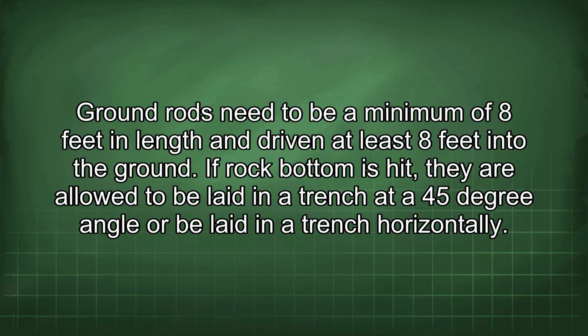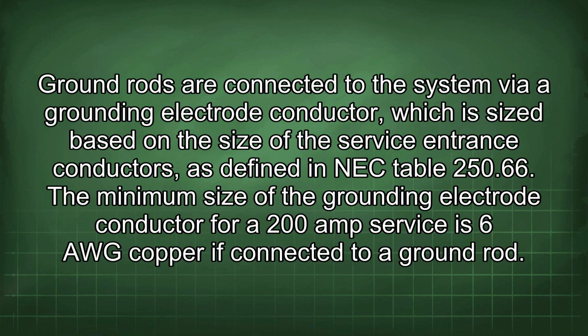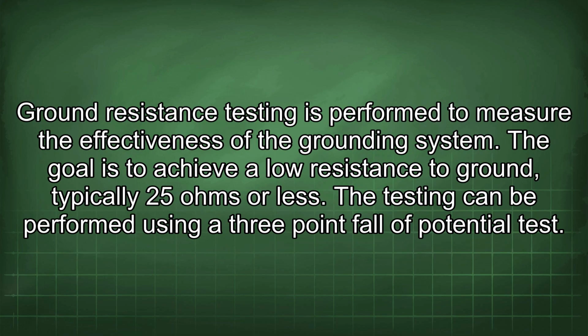Ground rods need to be a minimum of 8 feet in length and driven at least 8 feet into the ground. If rock bottom is hit, they are allowed to be laid in a trench at a 45-degree angle or be laid in a trench horizontally. Ground rods are connected to the system via a grounding electrode conductor, which is sized based on the size of the service entrance conductors, as defined in NEC Table 250.66. The minimum size of the grounding electrode conductor for a 200 amp service is 6 AWG copper if connected to a ground rod. Ground resistance testing is performed to measure the effectiveness of the grounding system.